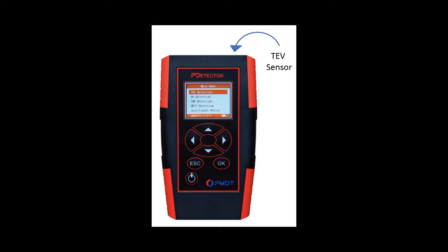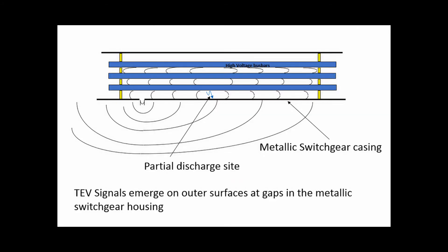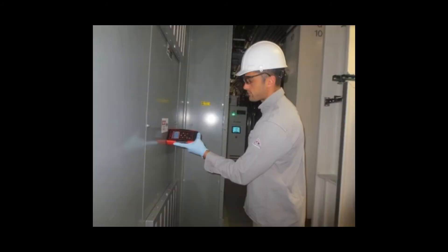TEV, or transient earth voltage, are induced voltage spikes on the surface of the surrounding metalwork. This occurs because the partial discharge creates current spikes in the conductor and hence also in the earth metal surrounding the conductor. TEVs are a very convenient phenomenon for measuring and detecting partial discharges, as they can be detected without making an electrical connection or removing any panels. While this method may be useful to detect some issues in switchgear and surface tracking on internal components, the sensitivity is not likely to be sufficient to detect issues within solid dielectric cable systems.